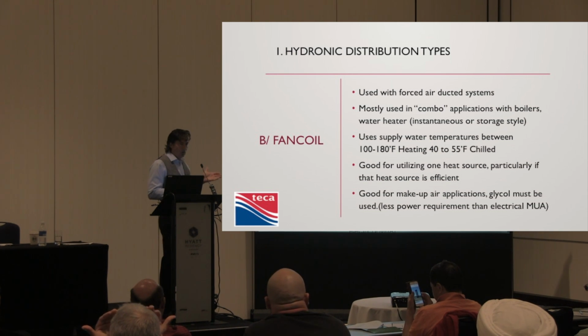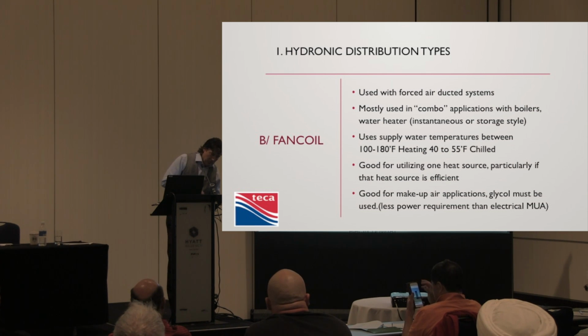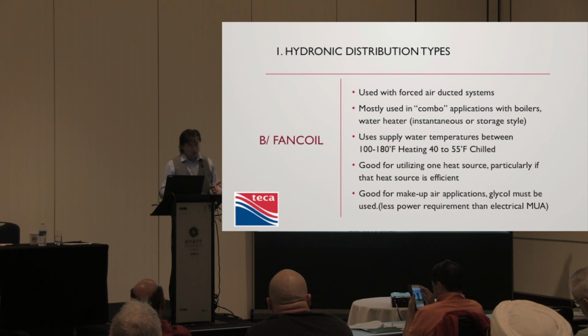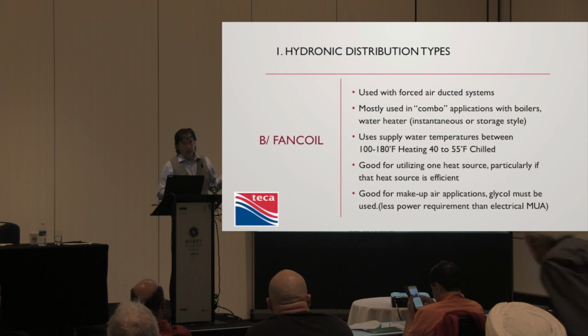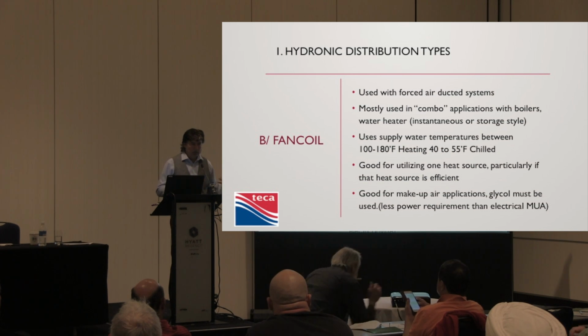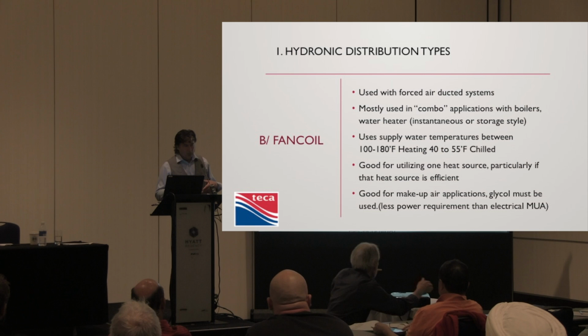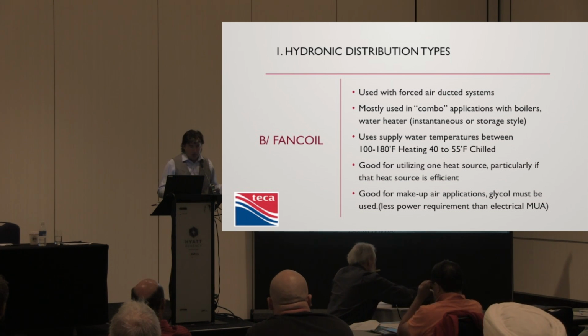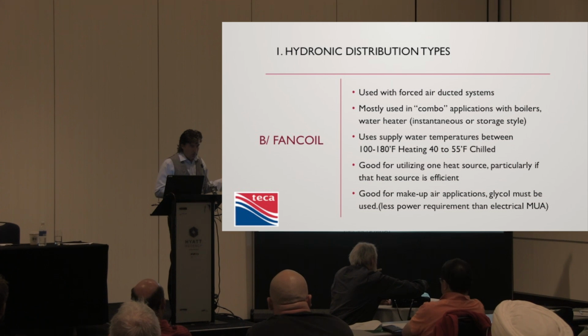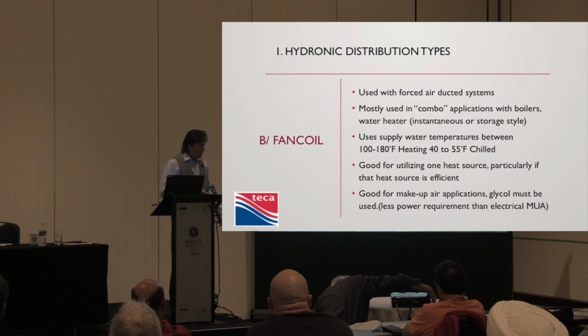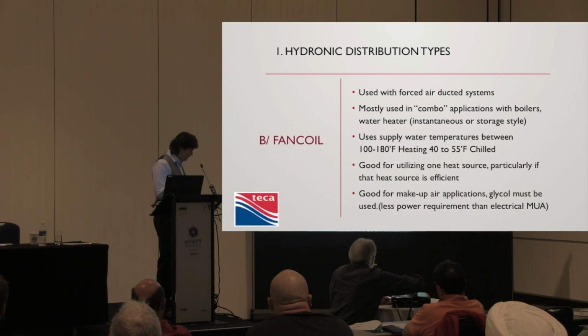Now, makeup air comes up a lot. Our ventilation code says, and I know you guys have come across this, everybody wants the 1000 CFM kitchen exhaust, but we've got a B-vented fireplace because that's the one they wanted. So you've got 1000 CFM going out. The code says, thou shalt replace 100% in any naturally aspirated fuel-fired appliance in the house. You have to replace 100% of the exhausted air if it exceeds 1/2 air change of the home. So this happens all the time. 1000 CFM of exhausted air is a mighty big home to not have to provide makeup air. So when you have to provide makeup air, it's quite a bit.